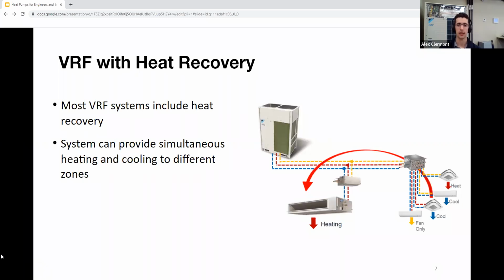Next, we have heat recovery, and with this type of system, every indoor unit can actually be in different modes. You can have one zone in cooling, one zone in heating. There's a different component here that you can see, and those are the branch boxes. Branch boxes come in various different sizes, and they're kind of like the traffic cops for refrigerant, and they let either liquid or gas through, depending on what's required for the indoor unit. And this is the most common type of VRF system used in commercial buildings. It depends a little bit on what type of space or indoor units you're looking at, but oftentimes it's preferred by the building owner or tenant to have this simultaneous heating and cooling ability.